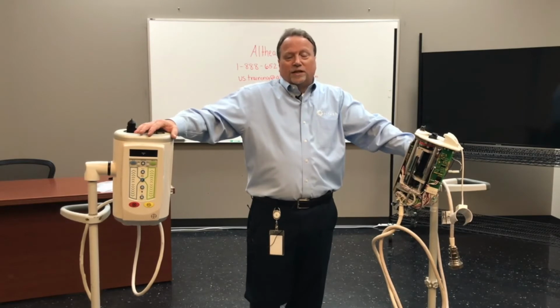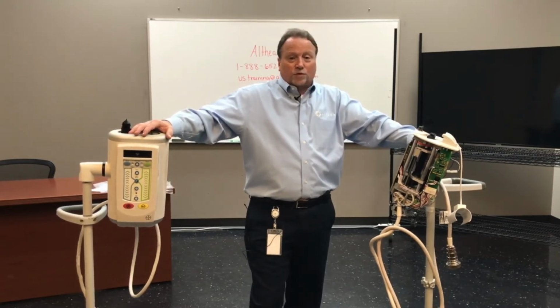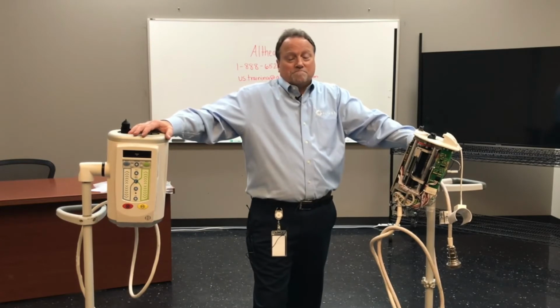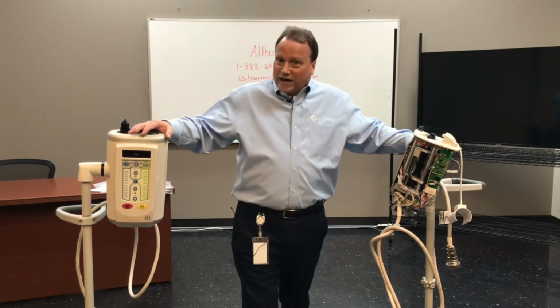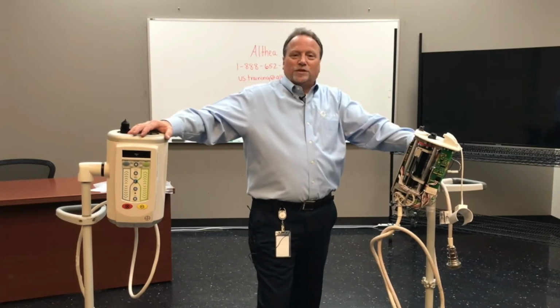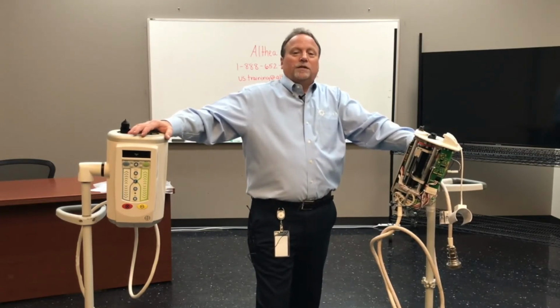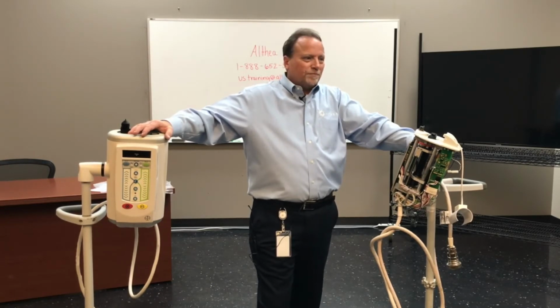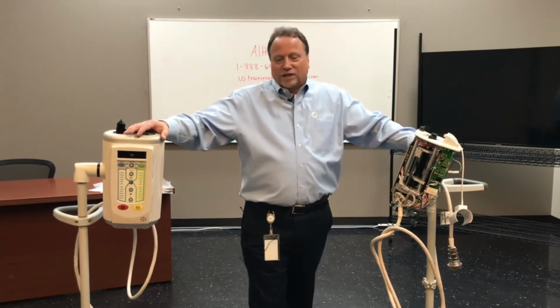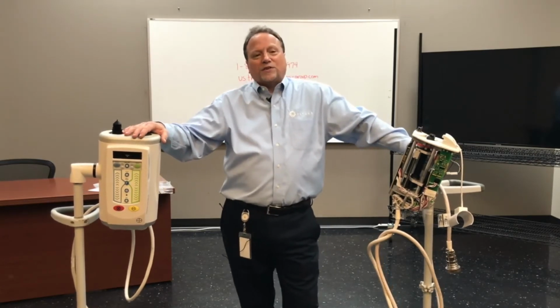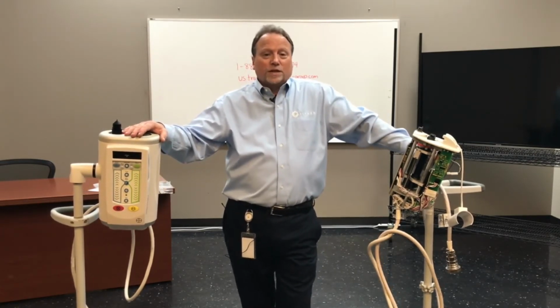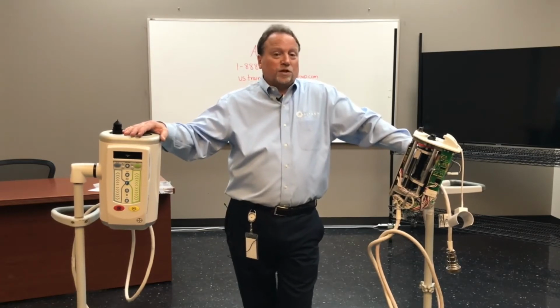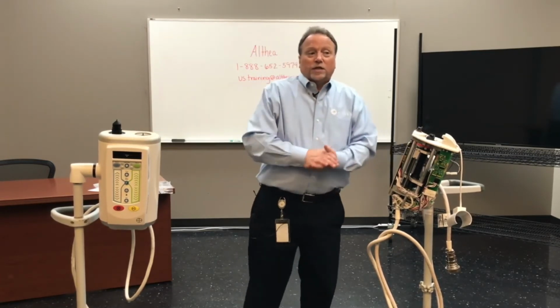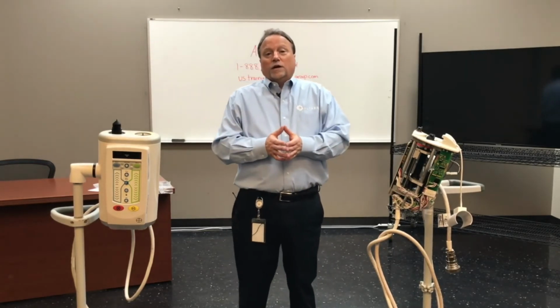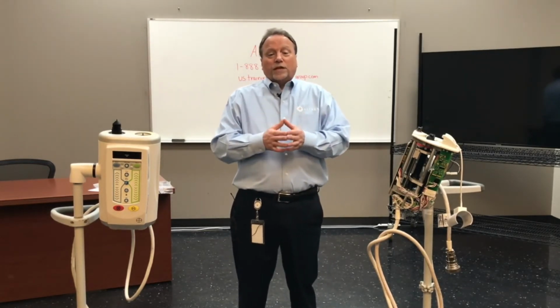Like I said, is software needed? I've never needed it. I've been doing PMs for over 15 years, and it's never been a problem. If I have been out of specs, I dug a little deeper and said, oh, so the motor's going bad. I replaced the motor, bam, right back into specs again with no problem. So you have some basic verifications that you have to look at. Some of the basic verifications is going to be volume. And the volume is: is it injecting 50 milliliters when it says 50 milliliters? And is it doing the flow? So you have flow and volume, and that's going to give you the time.